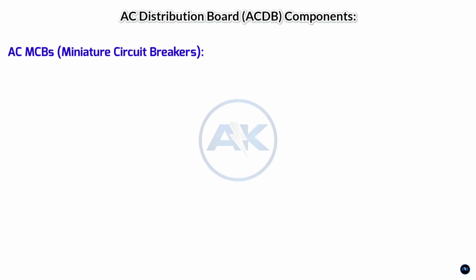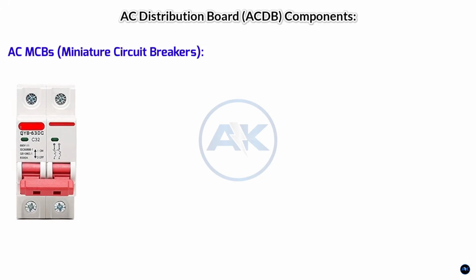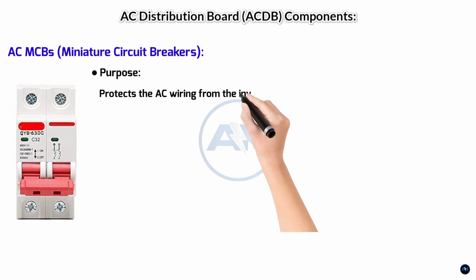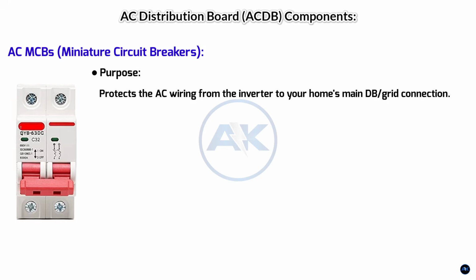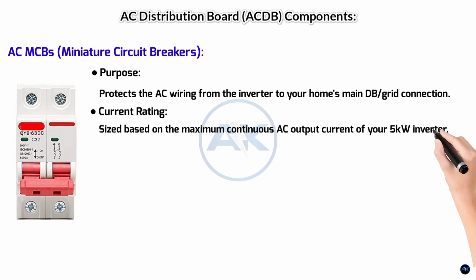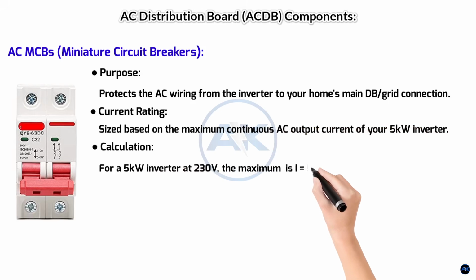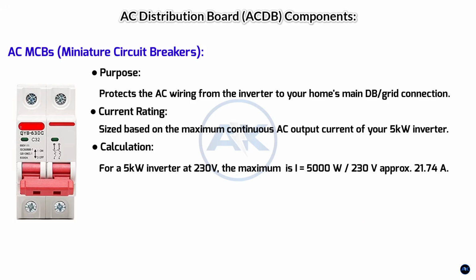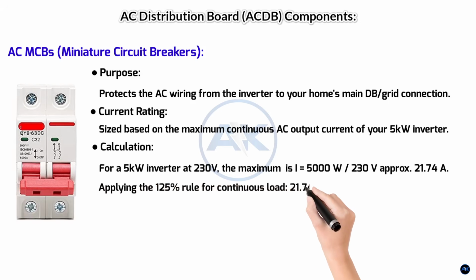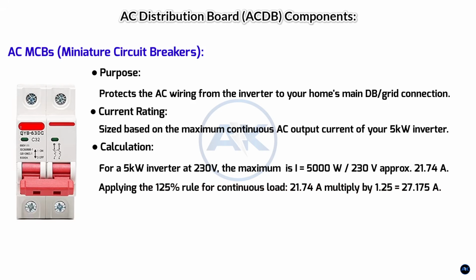AC MCBs, miniature circuit breakers. Main AC output breaker, inverter to load and grid. Purpose: protects the AC wiring from the inverter to your home's main distribution board and grid connection. It also serves as an isolation point for the inverter. Current rating: sized based on the maximum continuous AC output current of your 5 kilowatt inverter. Calculation: for a 5 kilowatt inverter at 230 volts, the maximum continuous current is I equals 5000 watts divided by 230 volts, approximately 21.74 amps. Applying the 125% rule for continuous load, 21.74 amps multiplied by 1.25 equals 27.175 amps.